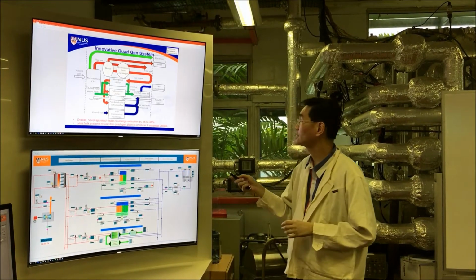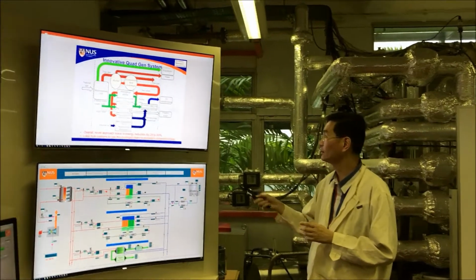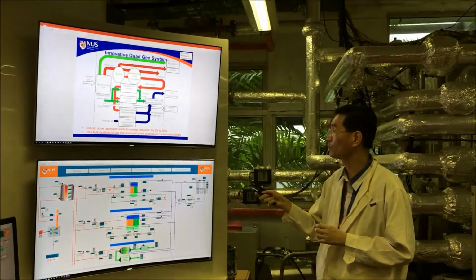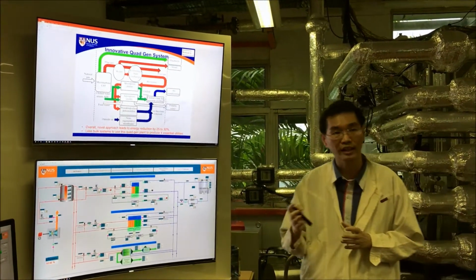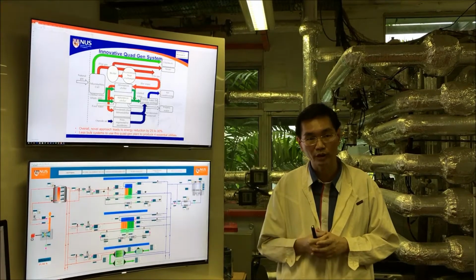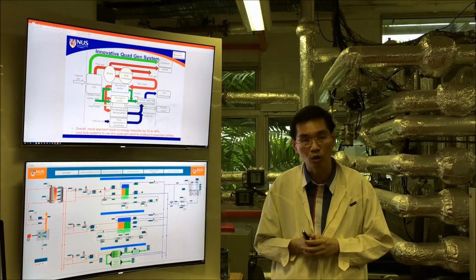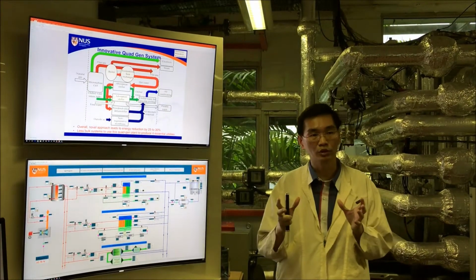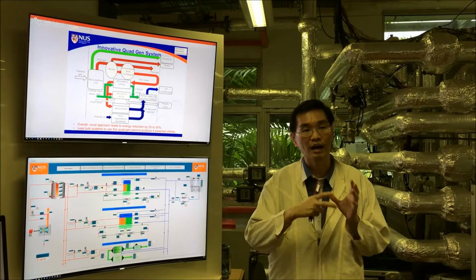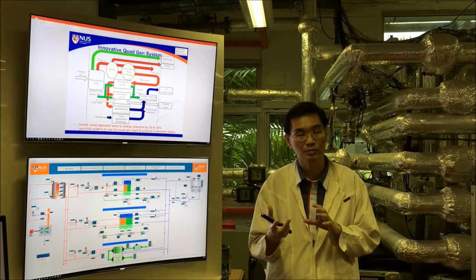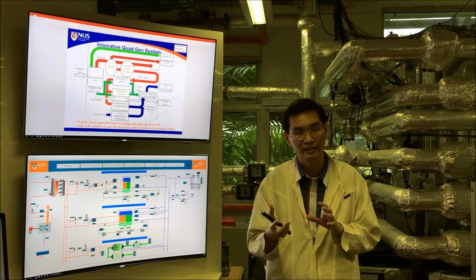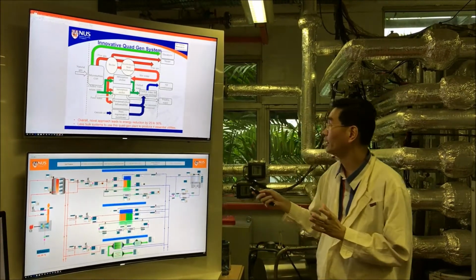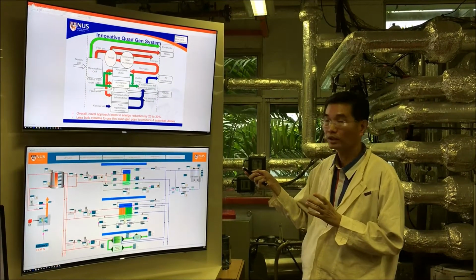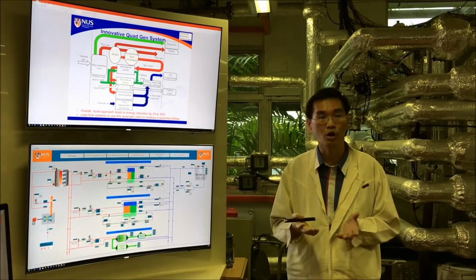As you can see from these schematics, it works in this manner. First, you feed in natural gas to the microturbine. The microturbine will generate electricity. In this case, there are about 2 microturbines. Each microturbine is about 65 kilowatt. The flue gas from the microturbine while it's generating electricity will be harvested. In this case, the flue gas is about 200 to 250 degrees C. This harvested flue gas will be utilized in the boiler to produce either steam or hot water.